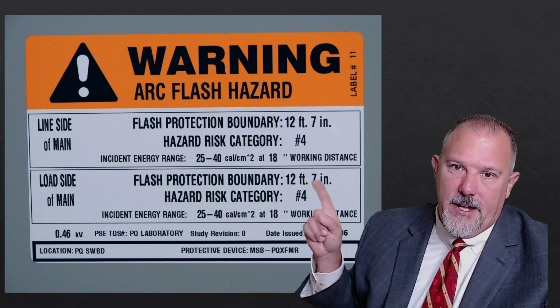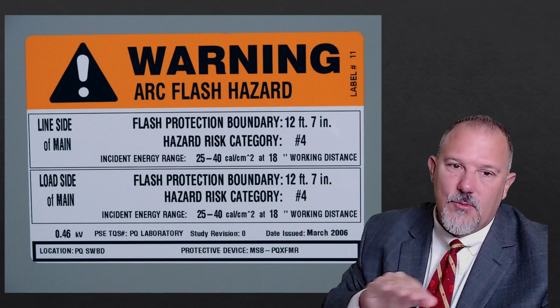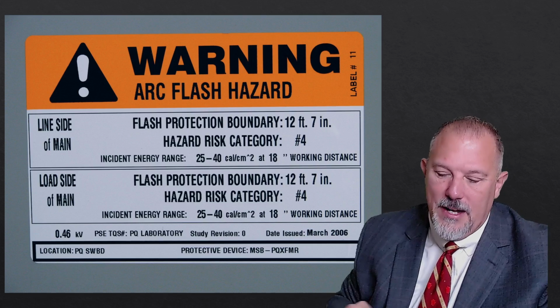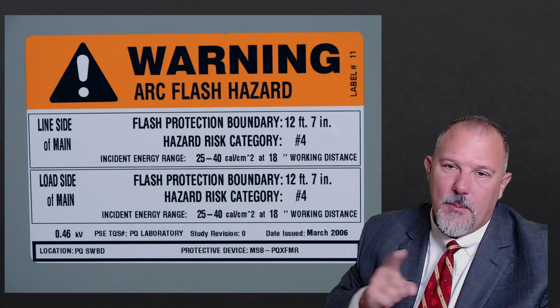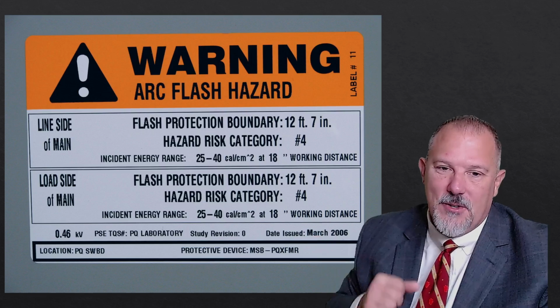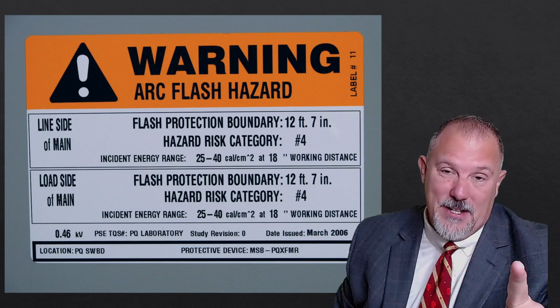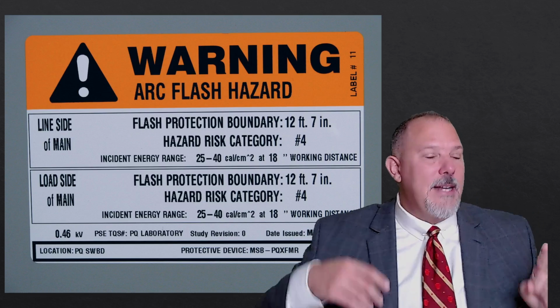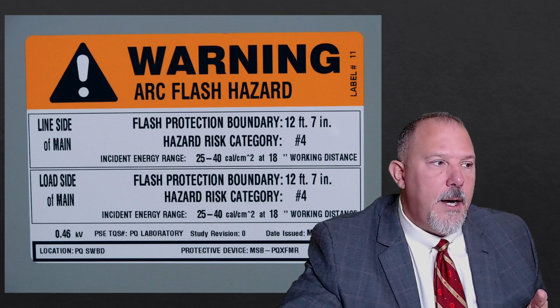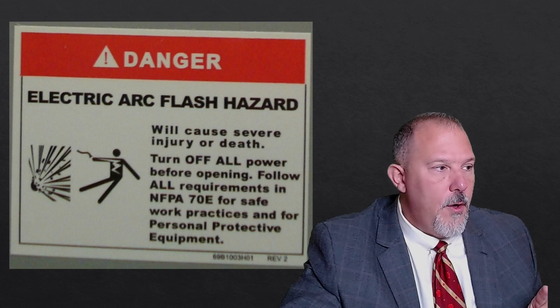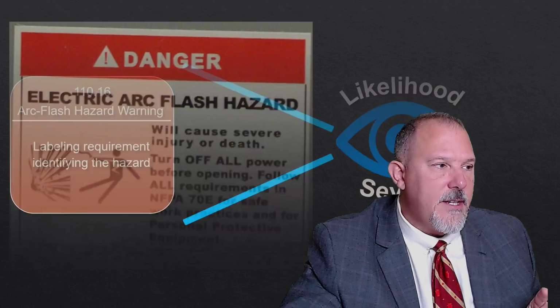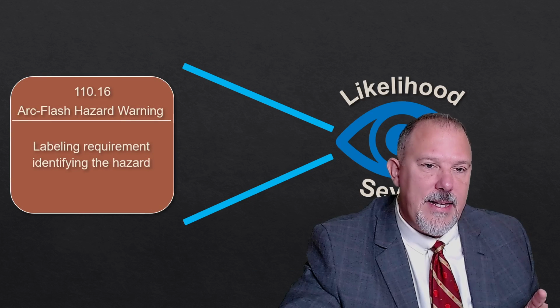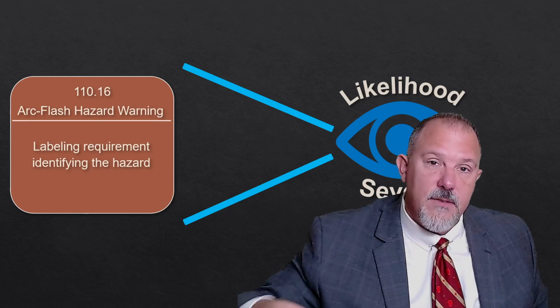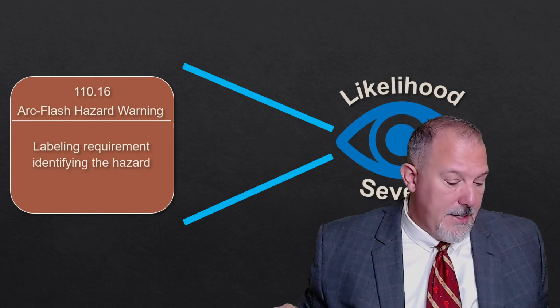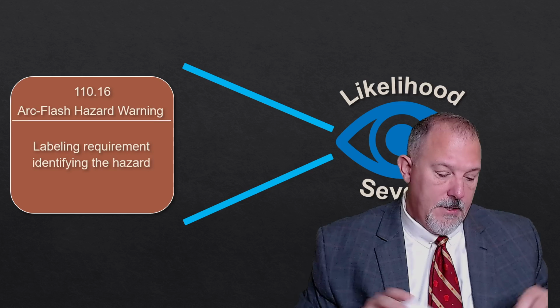Now, I'll just point one thing out, just for all of you 70E guys out there, you'll notice this is an old label. It has hazard risk category. We don't do hazard risk categories anymore in 70E. So that's an old label. Probably a bad choice on my part, but it was the easiest one I had to find. But in any case, if I have 6 disconnects, when I look in 110.16, do I have to label 6 fault currents, 6 different clearing times, on and on and on?